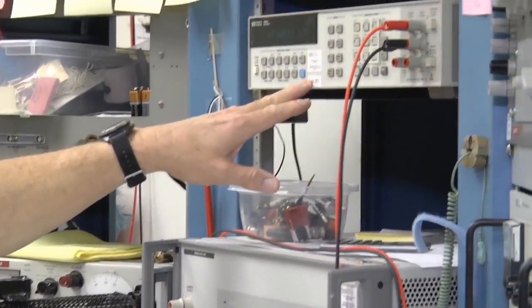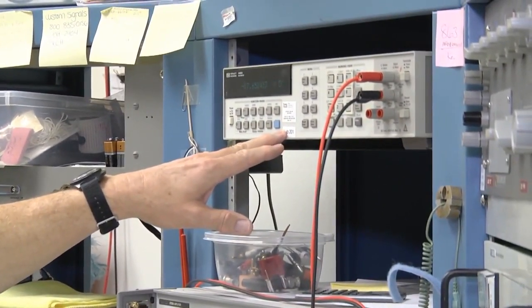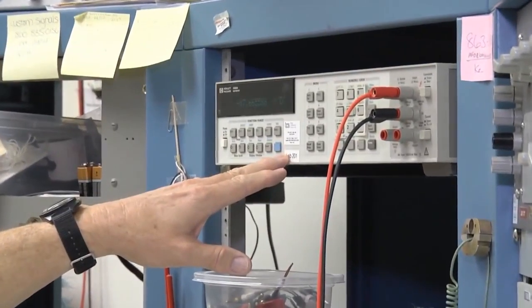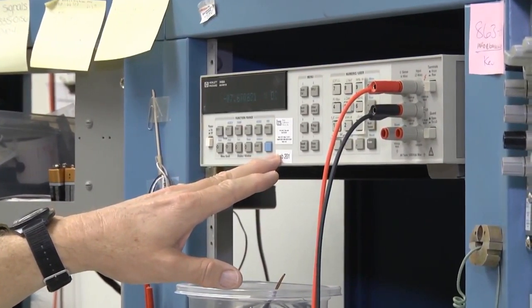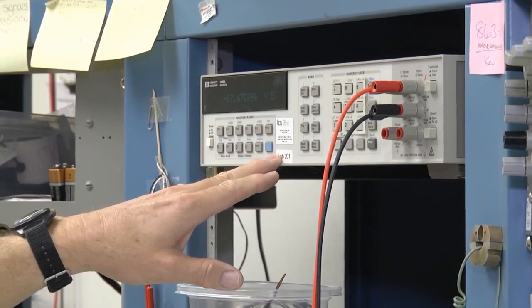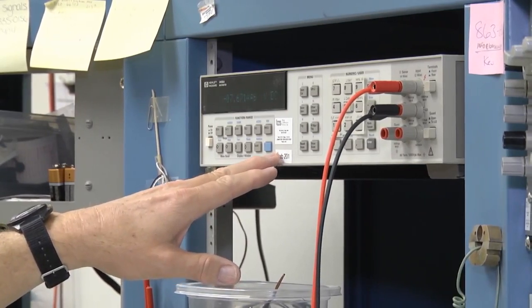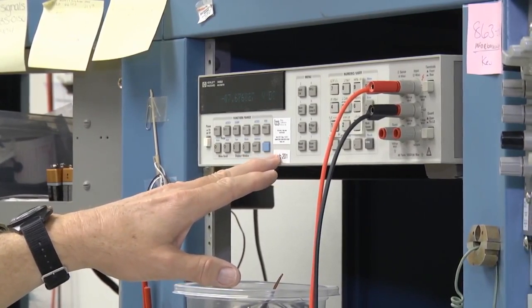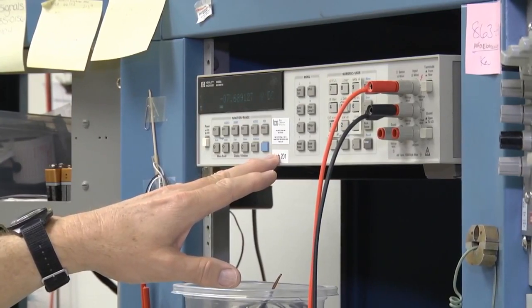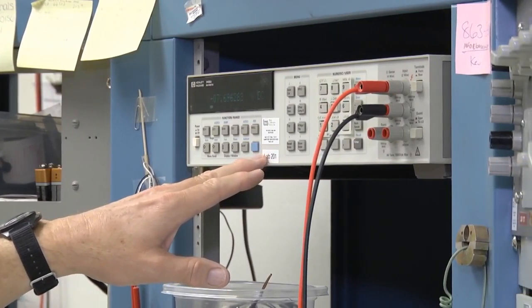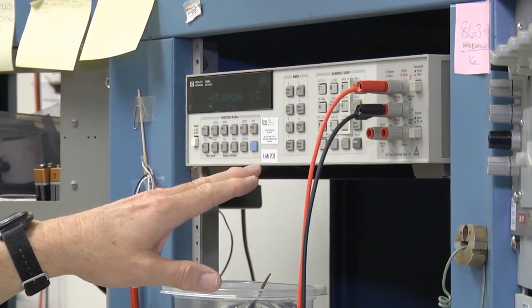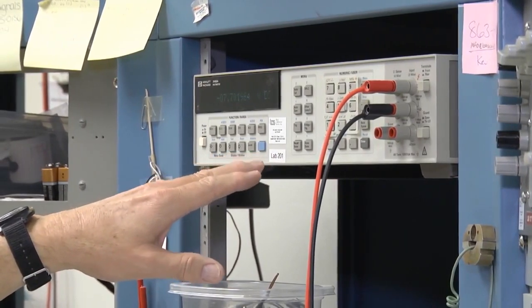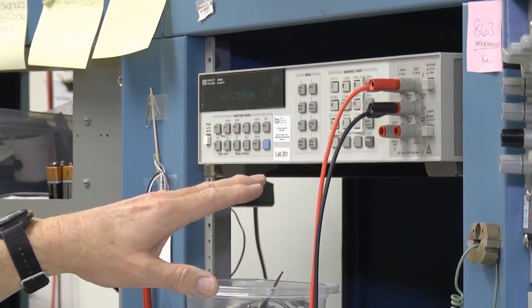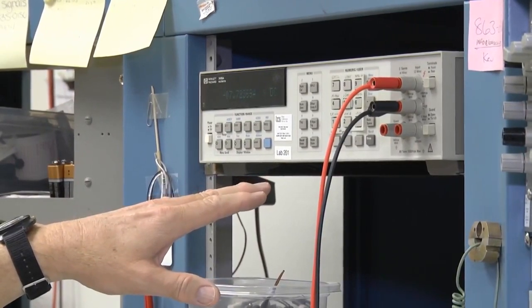Additionally, we utilize the Hewlett-Packard 3458A digital multimeter. We utilize the DC voltage portion of that to calibrate the DC voltmeter part of power supplies, and then the meter is also used in conjunction with the current shunt to calculate the current. We also utilize this meter in the AC voltage function so that we can monitor ripple coming out of the power supply to ensure that the ripple meets the manufacturer's specification.